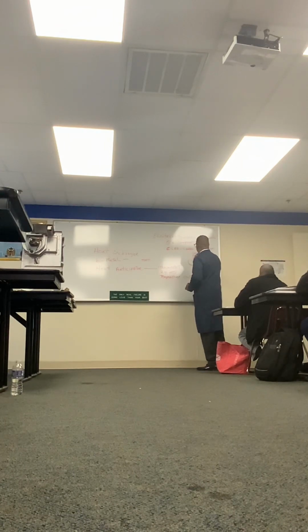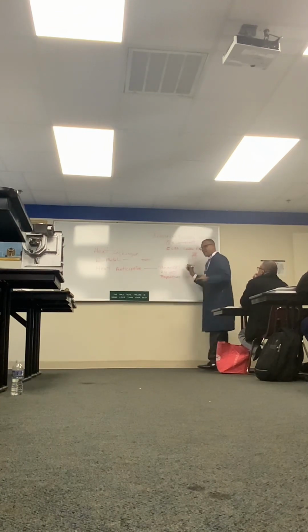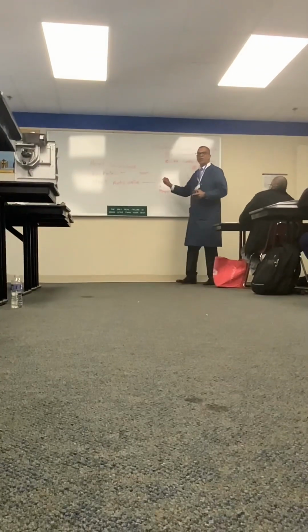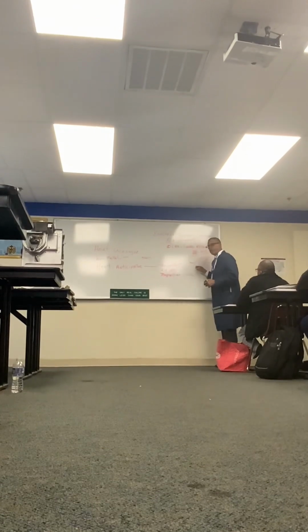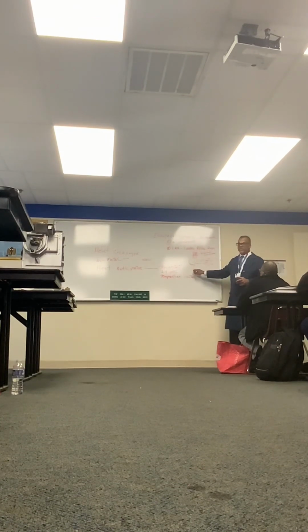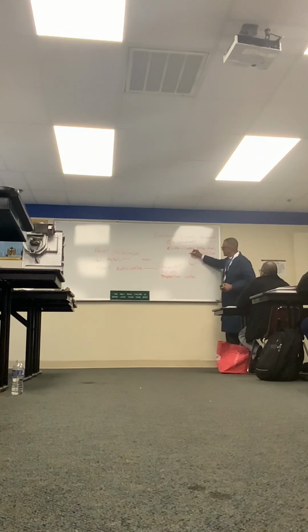And so this is coming straight off of L1 and L2, and when we close this, it's not a contactor, it's a what? Service disconnect. So it's disconnecting power to that unit if you wanna work on it. Or you're gonna get torn off the frame with 240, if you touch that. So you always take the switch and put it to the off position.